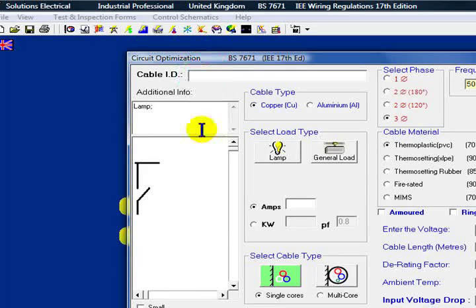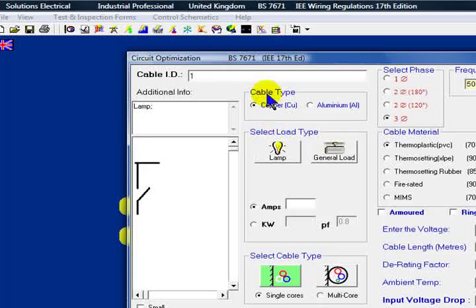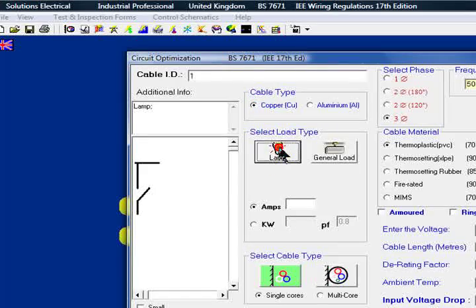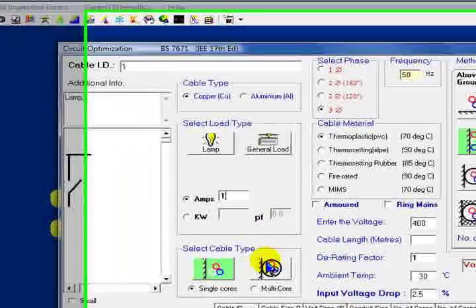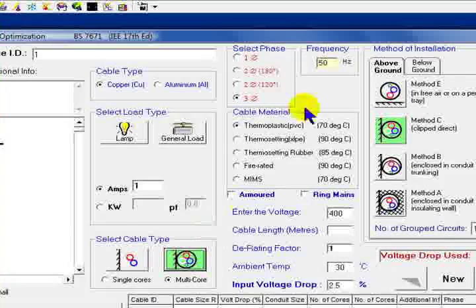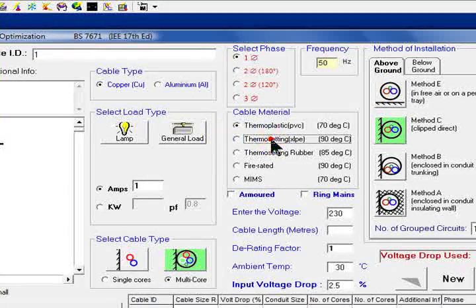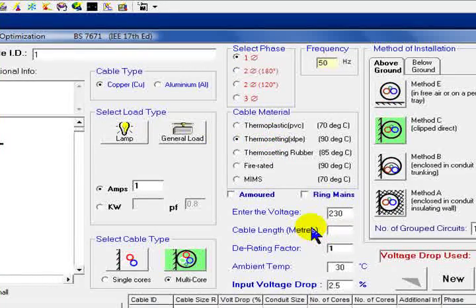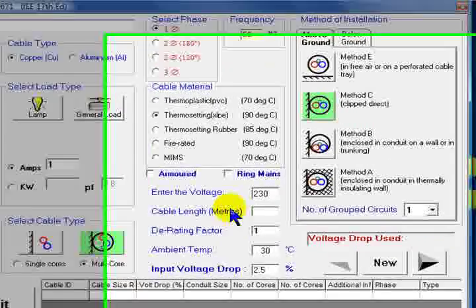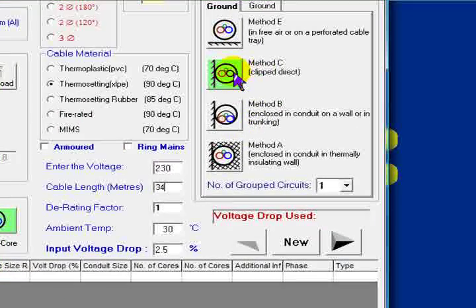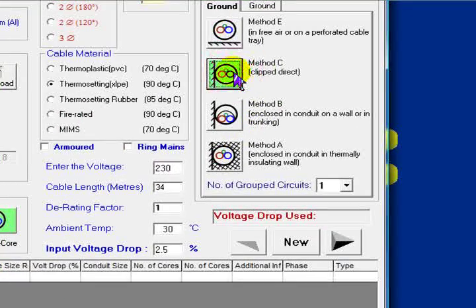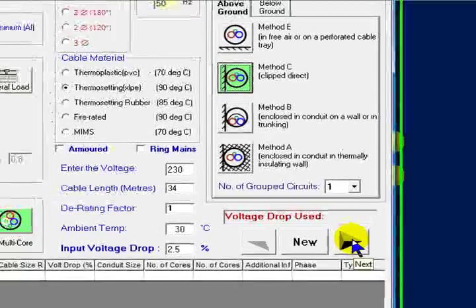We'll come up here, our first cable, give it an ID. We'll call it number 1. It's in copper. We'll have it a lamp, a load of 1A, a multicore in a single phase, 90 degrees C. The length of our run will make it 34 meters. Have it clipped direct, and we'll just go straight over here to our next cable.